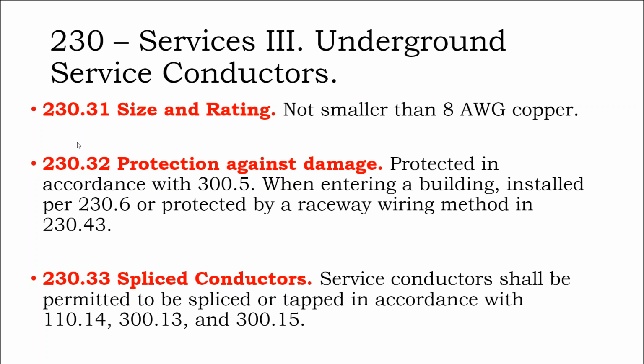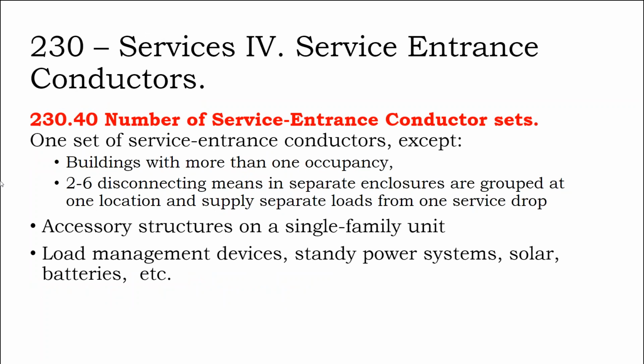All right, so we have the underground service conductors, not smaller than number 8, which is pretty small to begin with, but I guess if you're doing very small service panels, that might give you a minimum size of powering a panel. Protection from damage where entering a building, they kind of punt that to just slightly later. Splice conductors, they say, hey, we're going to talk about splicing and wiring methods a little bit later in the general section. So we're going to bump into that.